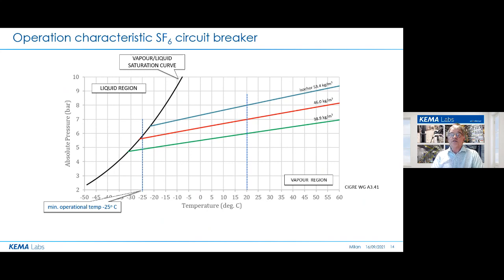Well, we need to understand a little bit of how and why the new gases work from a thermodynamical point of view. What we see here is the phase diagram of SF6, a chart predicting at what pressure and temperature the SF6 gas condenses, so will lose its power, because only the SF6 works as a gas. Apart from current and voltage, a very important parameter of the switchgear is its minimum operational temperature.